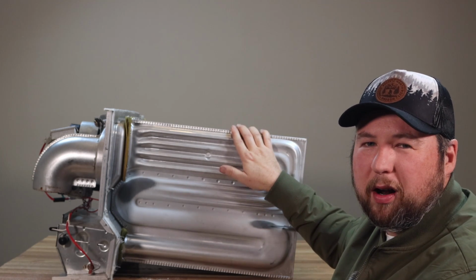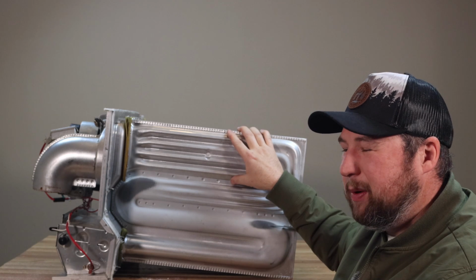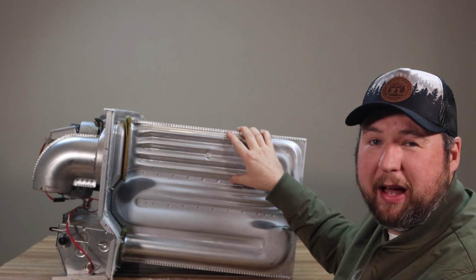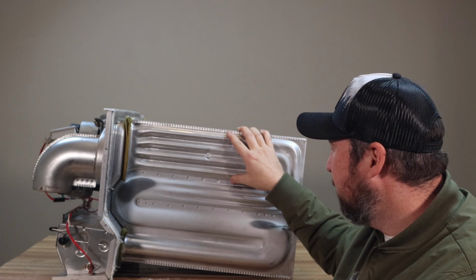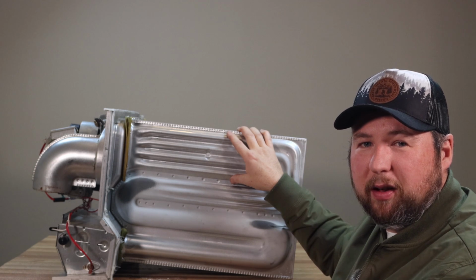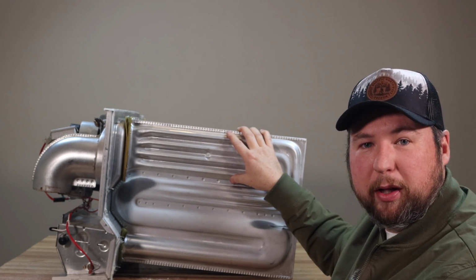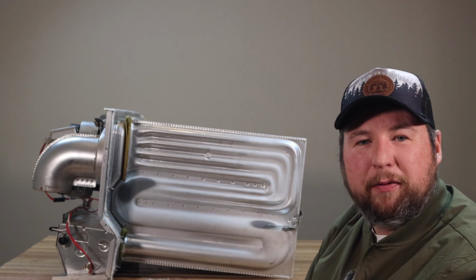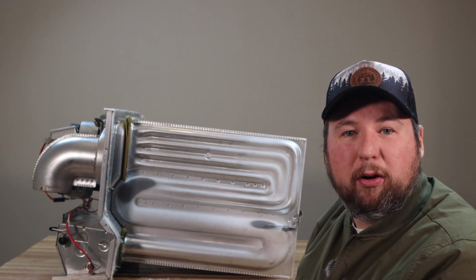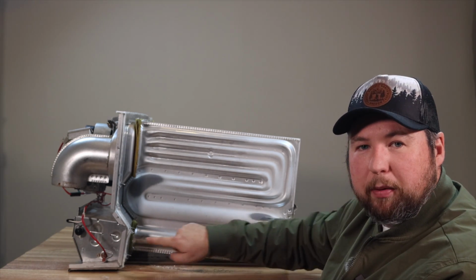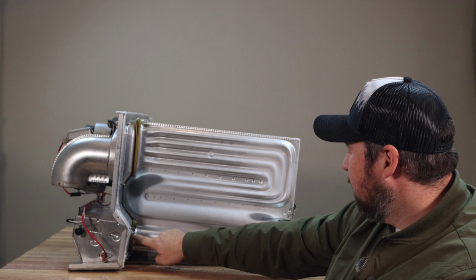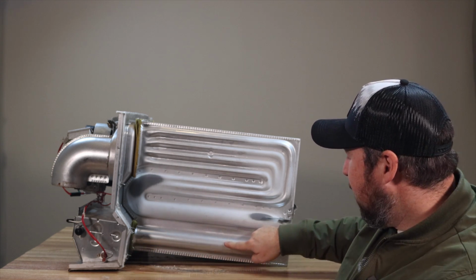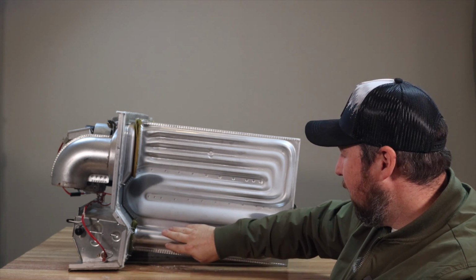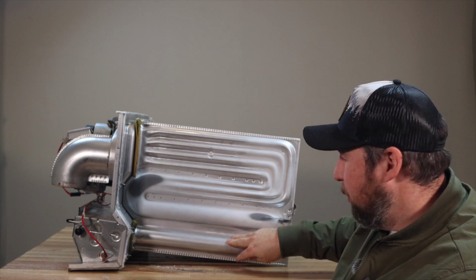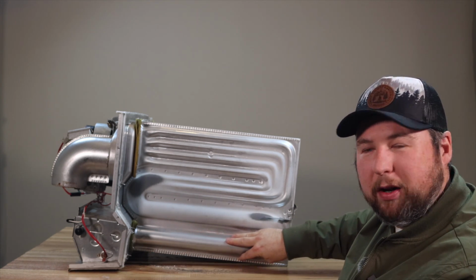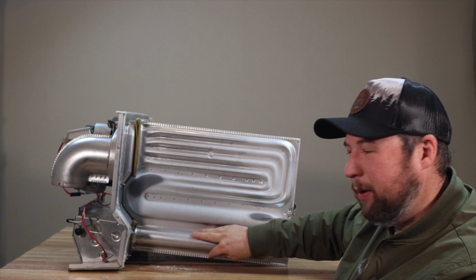These are probably the more common heat exchangers you're going to see, just because for the manufacturers they're a lot easier to mass produce, and they're pretty solid. For the most part, if you have a good install, they're not really going to fail unless they're extremely old or you have some kind of external force that's causing them to fail early. But basically down here, this is where your burners are. So your burners are right here. It's going to shoot your jet of fire through here, right? And this area is considered the combustion chamber, because this first chamber is where it's combusting. That's where it's shooting in your flames.